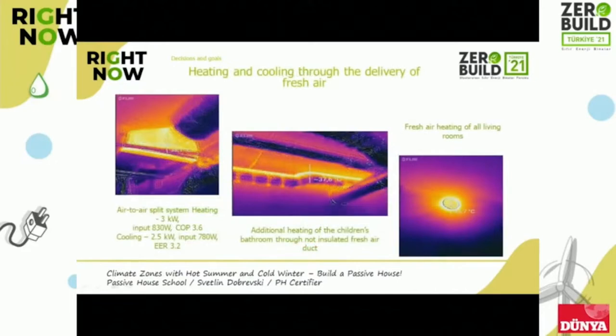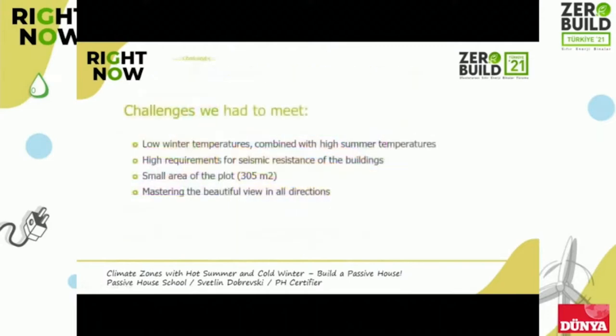In order to take all advantages of the passive house standard, we decided to use heating and cooling through the delivery of fresh air. The main reason to take this decision was to use the fresh air for heating. Using the fresh air for heating saves up to 80% compared to the radiators or floor heating. And from the other side, using the fresh air for cooling has significant benefits as well. First, the airflow is very low. And second, the noise levels and the risk of drafts are significantly reduced.